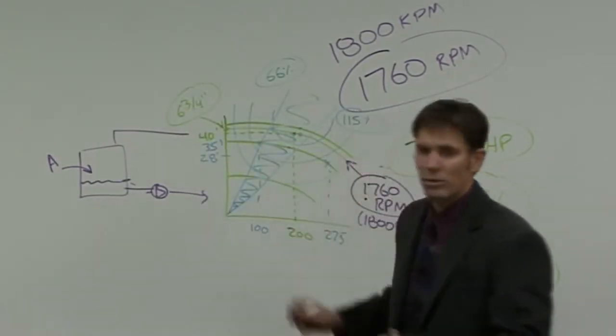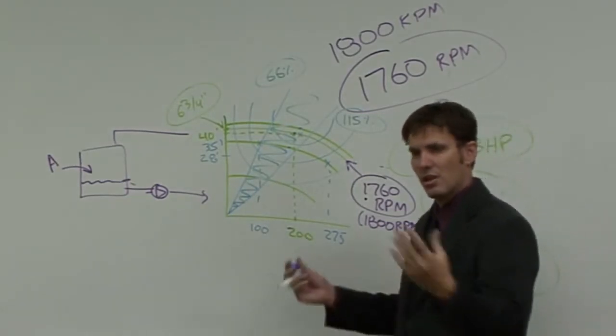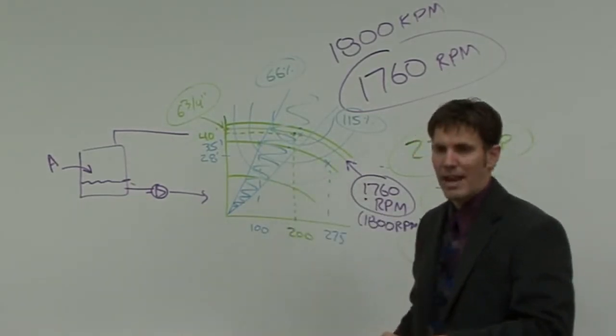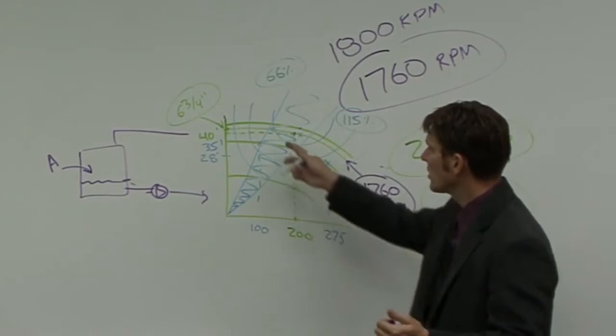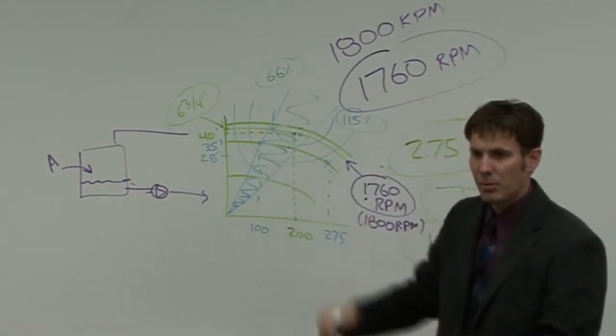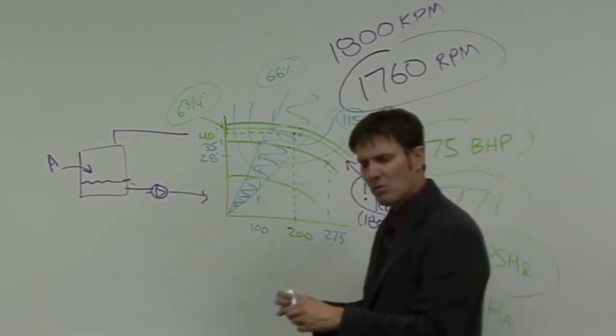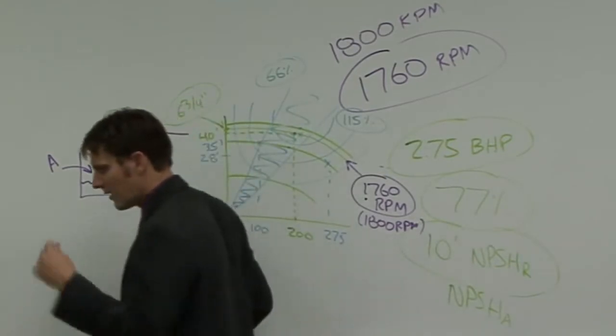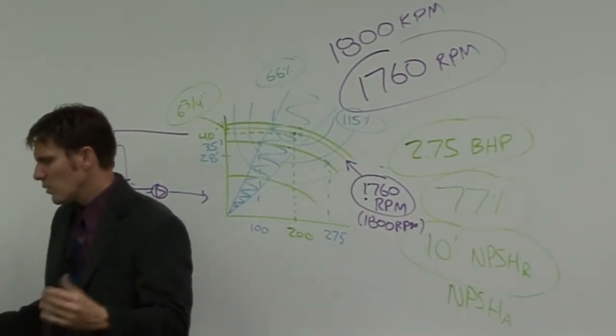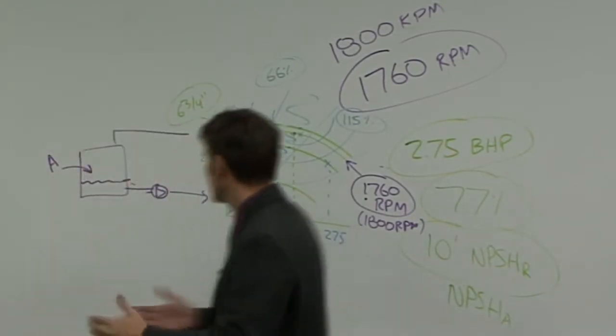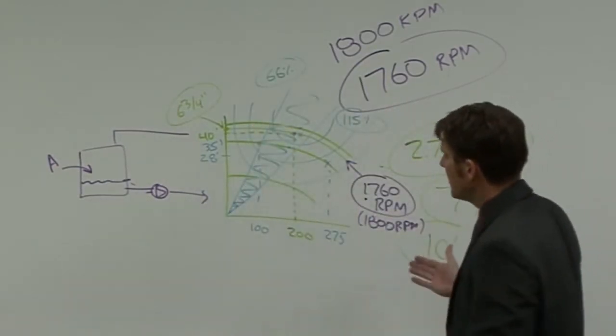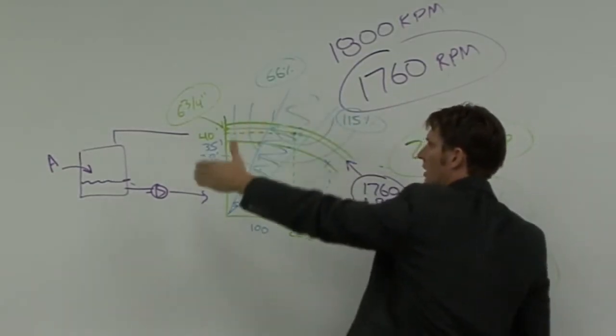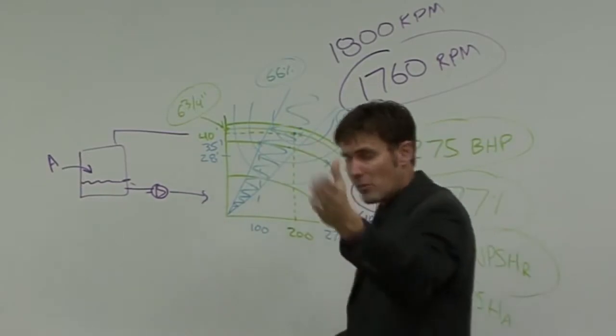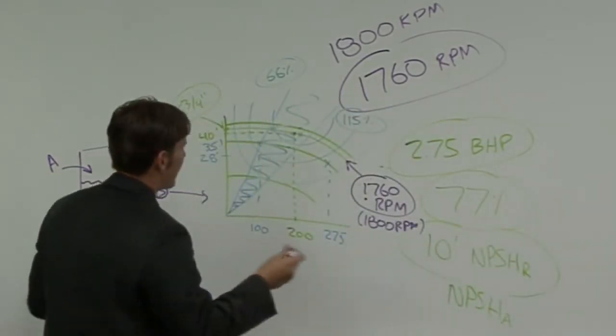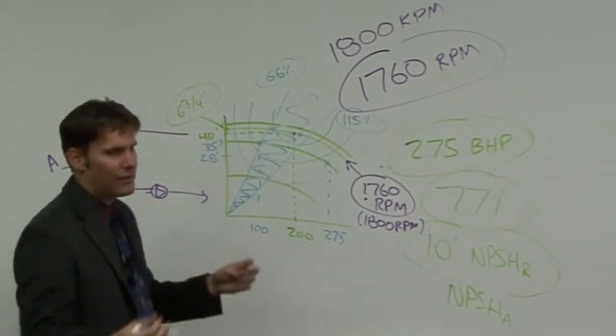Now, there are times where we just simply can't, because our condition's too crazy and we don't have pumps to match it. But when we have that option, where we're picking multiple pumps, that's where we'd want to focus. And we'll talk about that when we look at some of these pump curves. So we can tell this program that we could select to the left or to the right. Typically, you'd want to select to the left, and the reason that ASHRAE allows us to do this is that engineers are putting safety factors on their head values.